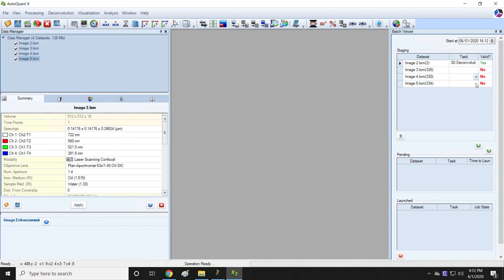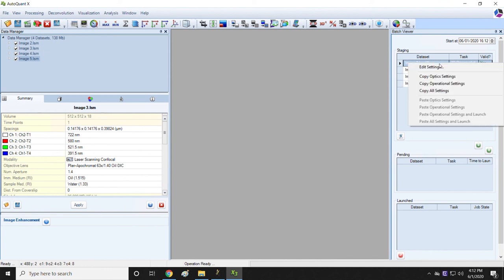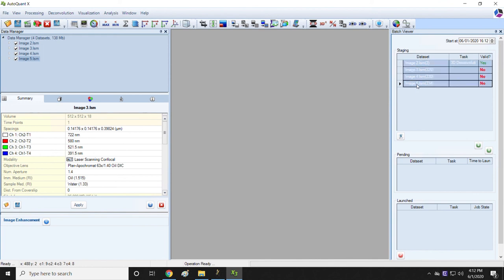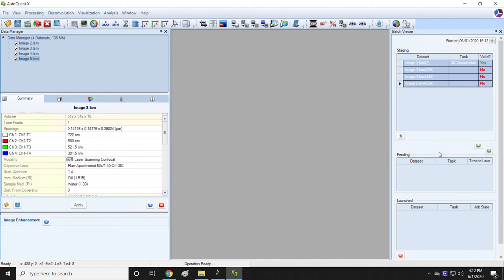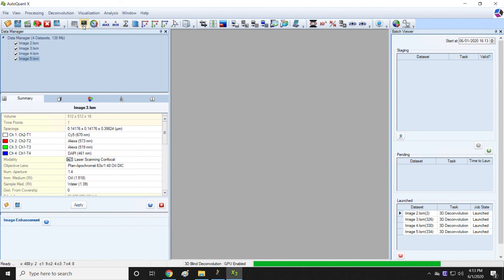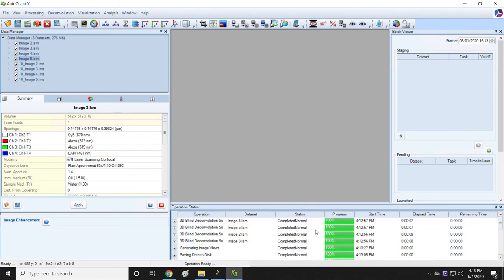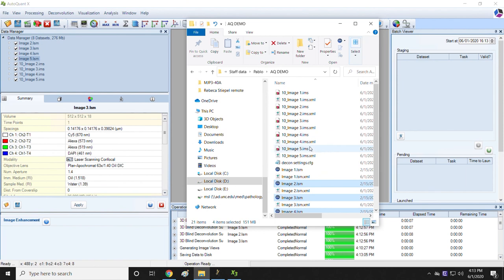The way I'm going to solve that is I'm going to click on the first one. I'm going to right click. I'm going to say copy all settings. Then I'm going to select all of them and apply the settings to all of them. To select all of them, I actually have to do it here. If you shift click on the name, it doesn't work. You have to shift click on the column and other work. Then I'm going to right click. This I have to do on the name and say paste all settings and launch. What I'm going to do is basically put all the settings that were in image two on all of the other ones and just launch them. There they went to the pending area and then the GPU grabbed them and it's working on them. If you want to see the progress, you can click here. It's just blazing through them and it's done. Now if we look here, we have all the deconvolved files. Note that the deconvolved files have a 10 underscore. That's just how AutoQuant automatically names things that it deconvolves.